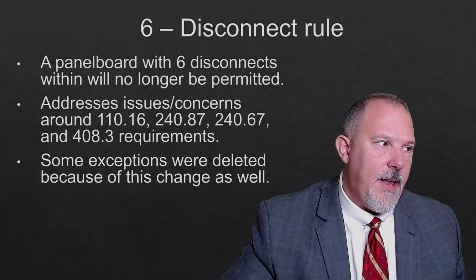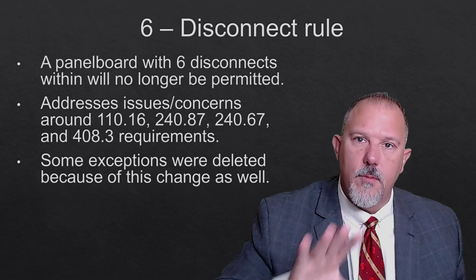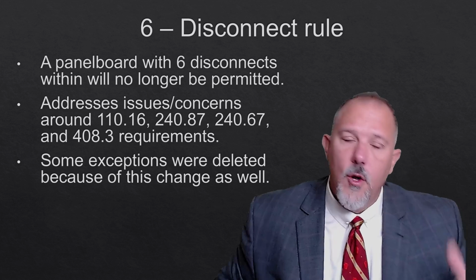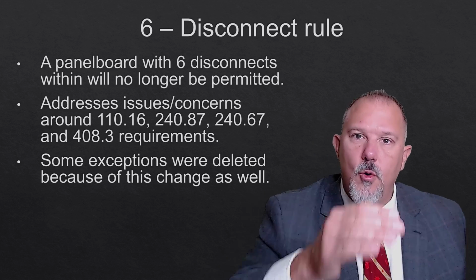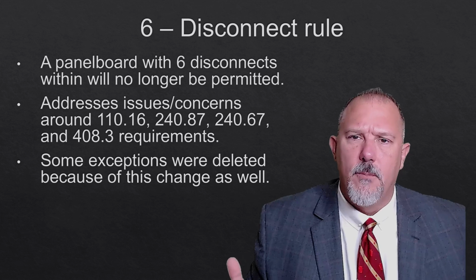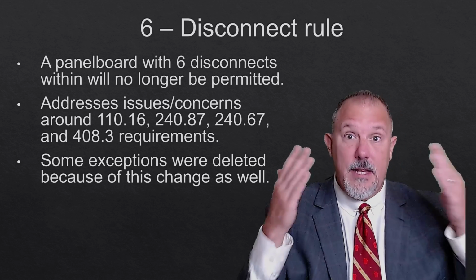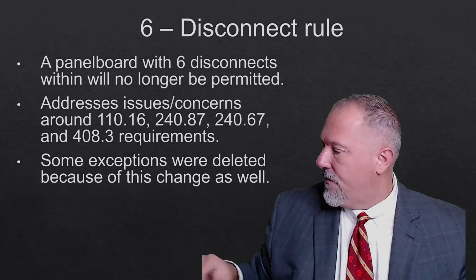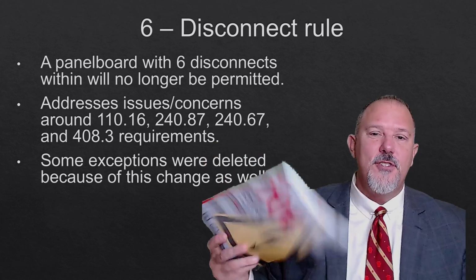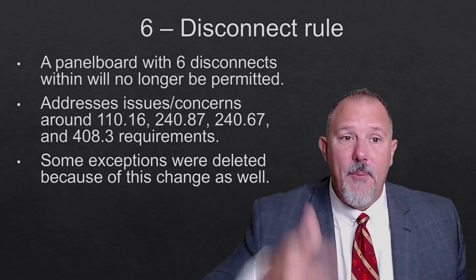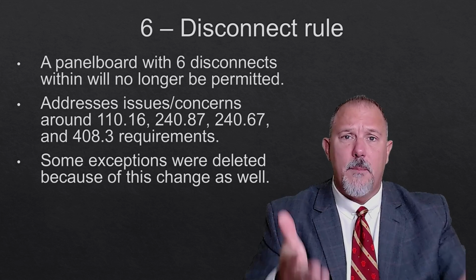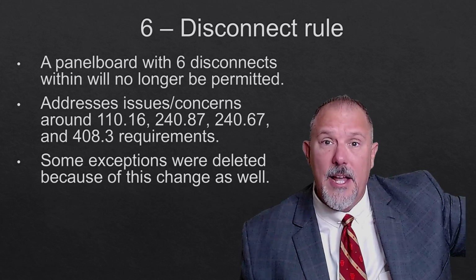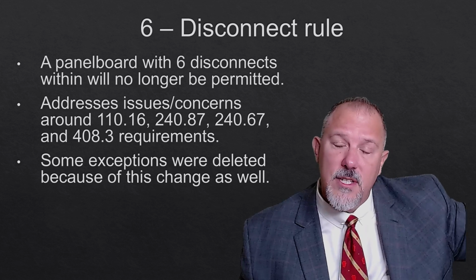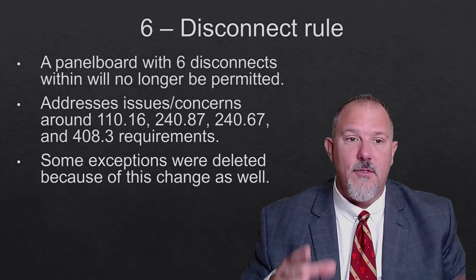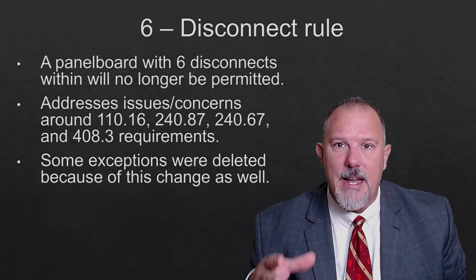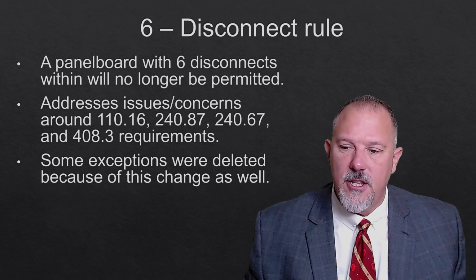changed things such that I will no longer see a panel board with 6 disconnects. Now think about it. Remember the labels. When people said, hey, if I have 6 disconnects in this panel board, I've got to put 6 clearing times, this doesn't make sense. And they said, well, the label doesn't make sense either for the electrical worker, because they're probably going to use it to try to apply the table method in 70E, but they're staring at bare copper conductor, the protection of which is handled by the utility on the line side of their transformer, which is that primary fuse, which is not going to open if I have an arc flash event, because it wasn't designed to provide that protection for me at this location in the power system.